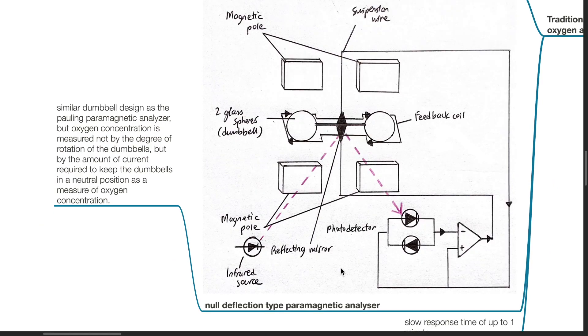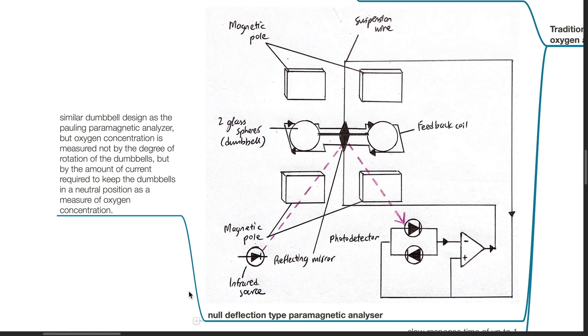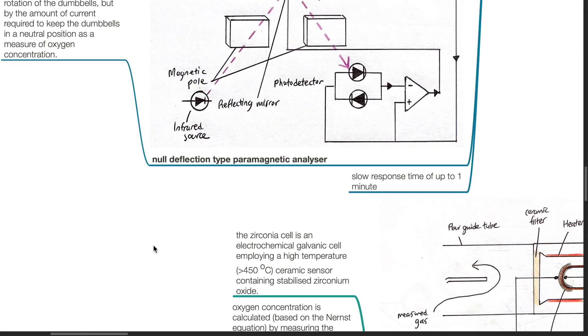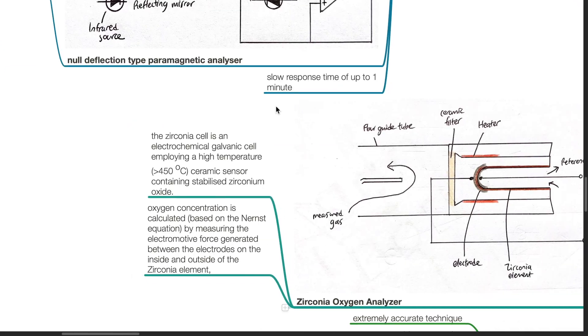The null deflection type paramagnetic analyzer has a similar dumbbell design to the Pauling analyzer. However, oxygen concentration is measured not by the degree of rotation of the dumbbells, but by the amount of current required to keep the dumbbells in a neutral position. It has a slow response time of up to one minute.